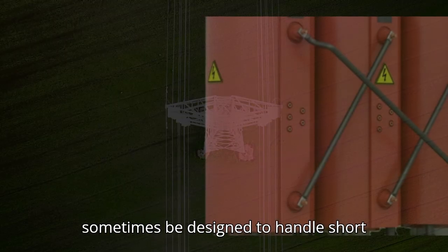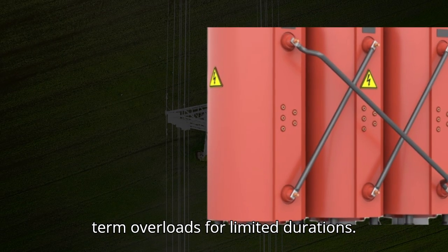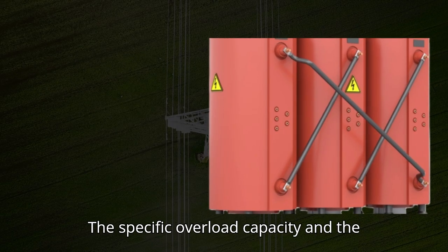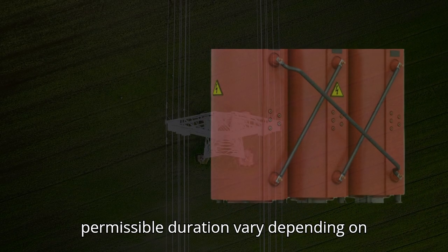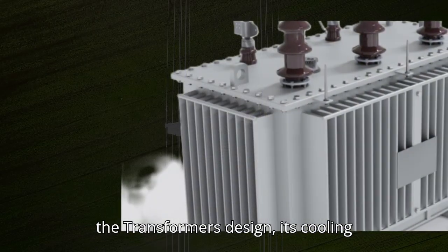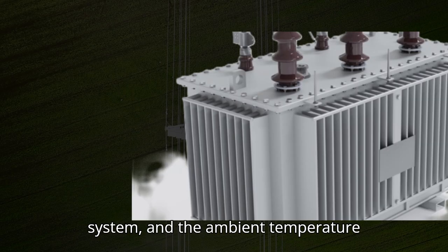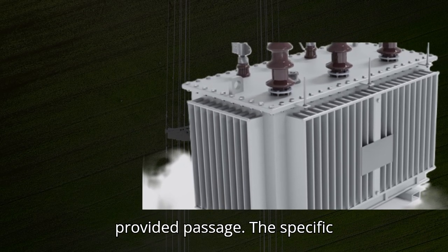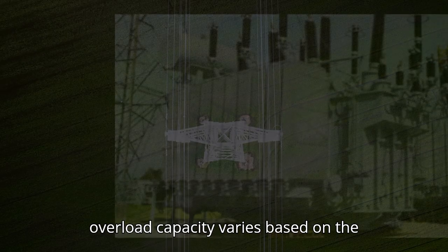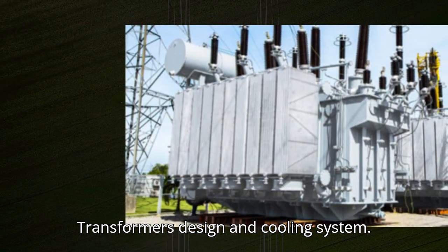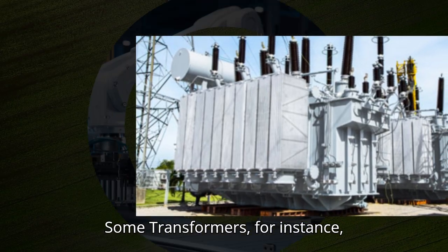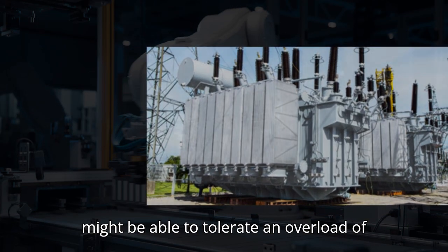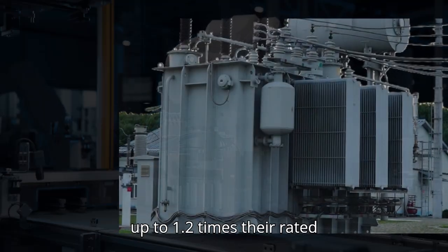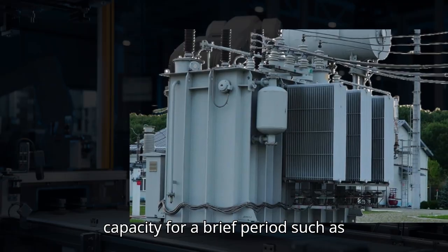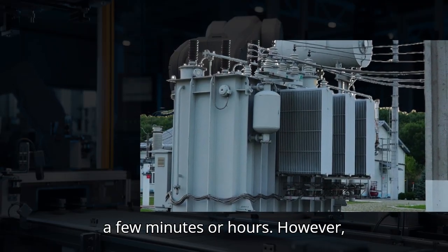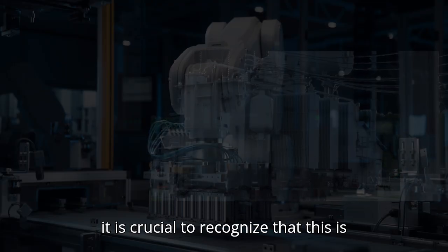While prolonged overloading is detrimental, power transformers can sometimes be designed to handle short-term overloads for limited durations. The specific overload capacity and the permissible duration vary depending on the transformer's design, its cooling system, and the ambient temperature. Some transformers, for instance, might be able to tolerate an overload of up to 1.2 times their rated capacity for a brief period, such as a few minutes or hours.